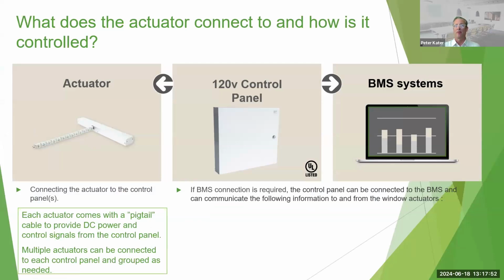The actuator has to be provided with power and control signals, and these come from a control panel. Typically, that's a wall-mounted cabinet like this, which is typically 120 volts. And then the low-voltage DC cabling to the actuator supplies 24 volts DC typically for the motor of the actuator. There's typically also a third wire, which is for data communication between the control panel and the actuator. This provides the ability to read the position that the actuator is in, in other words, how far open the window is at any point in time, and also for coordination between actuators. For example, if you have two actuators on a window that's too big for just one, they have to synchronize with each other so that they don't get out of sync.